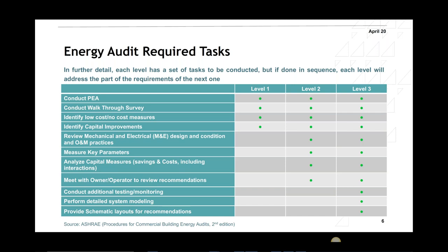We're going to see later what ASHRAE 211 tells you about what the savings are, how we're going to calculate the cost, basically the capital cost, what it should include, what it should not include. You should meet with the owner and the operator to review the recommendations. Sometimes you might come up with a recommendation that makes great sense to you, but it might not be a good option for the building for various reasons. So you need to speak to the owner, tell them what energy conservation measures you have, and then decide on the final list of EEMs or ECMs.